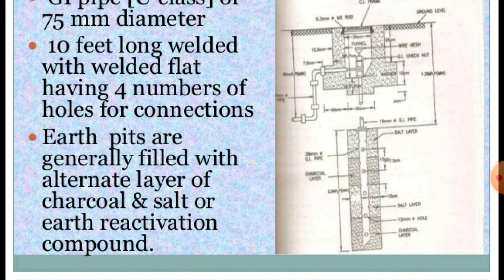So this is all about pipe construction. Here we have taken one galvanized iron pipe of 75 mm diameter, buried at 10 feet depth under the earth level, provided with 4 holes for external connections. And these holes are useful because the earth pit is filled with alternate layers of charcoal, salt and some other compounds, so that the moisture level is maintained inside the earth.